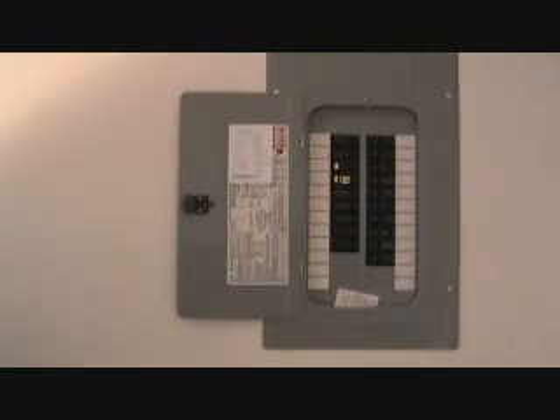Something else might be going on too. Here's an electrical subpanel, and it could be a bad breaker too. I don't know of any good way to check breakers. I've always been taught to find everything on the circuit first — check all that stuff out first — and then worst case scenario, change your breaker. I don't want to go to the store and pay $35 or $40 for a breaker and find out it's a $2 light switch or a loose wire nut.